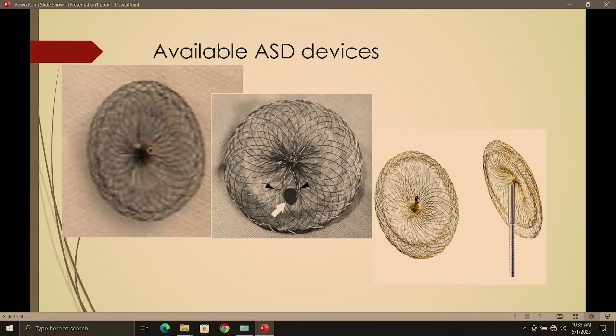So for the device size selection, without balloon sizing, the waist should be 2 mm greater than the largest size on transesophageal echocardiography. Waist 1 to 2 mm greater than the sizing balloon diameter in stop-flow diameter of the septal defect. Waist 1 to 2 mm greater than the largest size measured on color by transesophageal echocardiography. But in case of rim absence, it has to be taken 2 to 4 mm more than the size of the actual defect. And the LA must be able to accommodate the device.